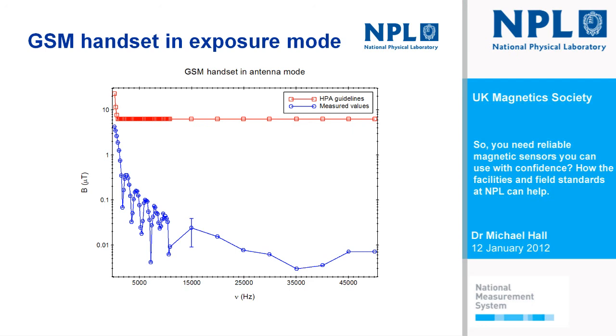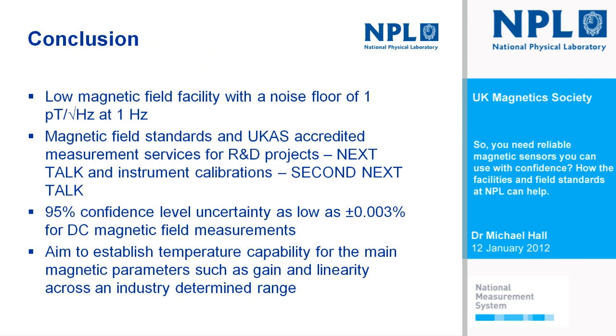And the next talk by Doug will talk about the ESA project that has been running, and we're calibrating the gradiometer at NPL now. And also we do instrument calibrations for instrument manufacturers like Bartington, and that'll be the talk after Doug. We have a very low uncertainty, 0.003%, and what we are always doing is looking to continually update and improve those facilities.